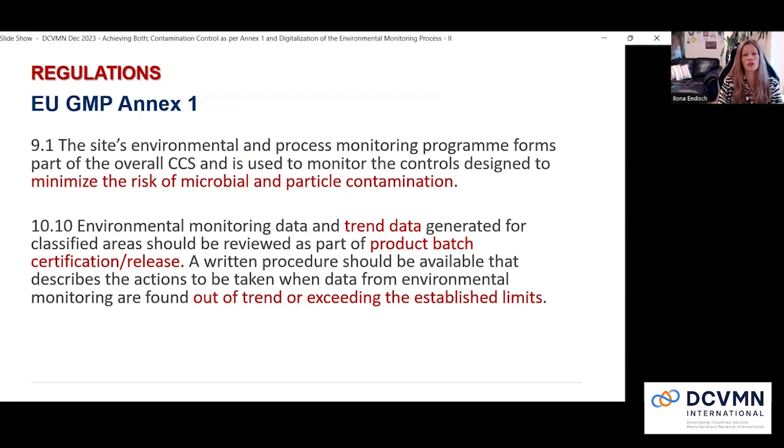So this version of Annex 1 actually focuses quite a bit on trending. Trending is mentioned 22 times in this revision, in comparison to the previous revision, where it was only mentioned once. So in this case, digitalization in the form of an environmental monitoring trending system can greatly assist.